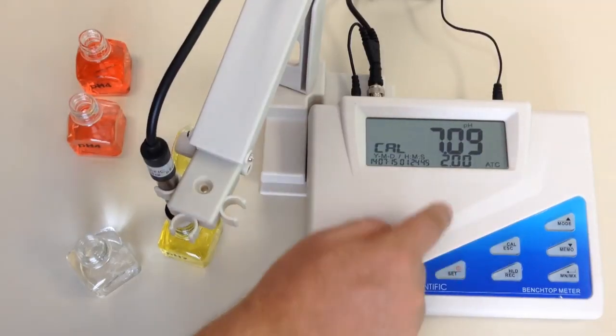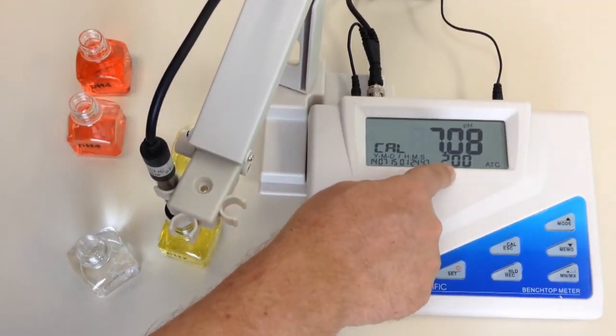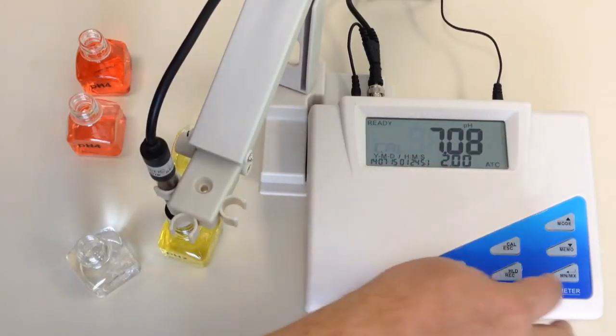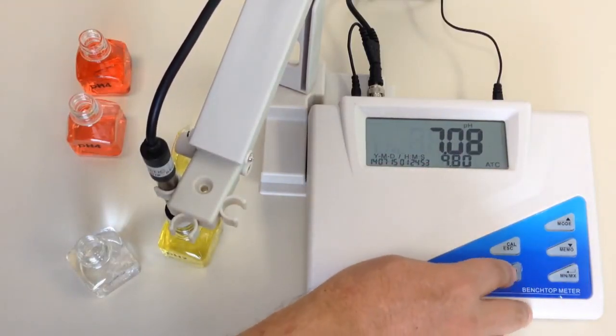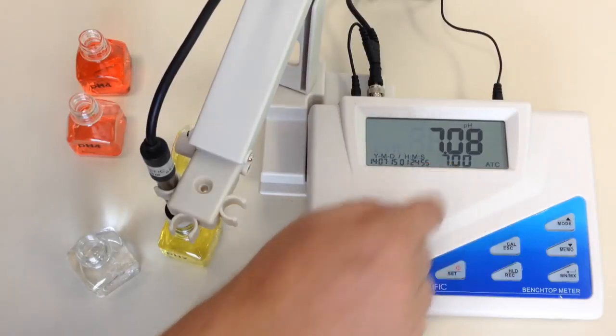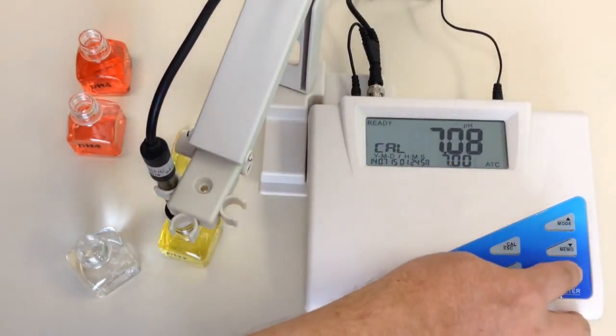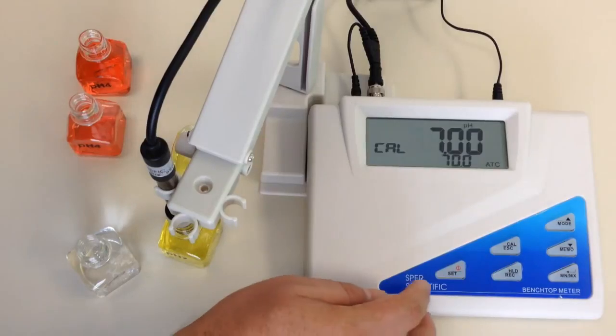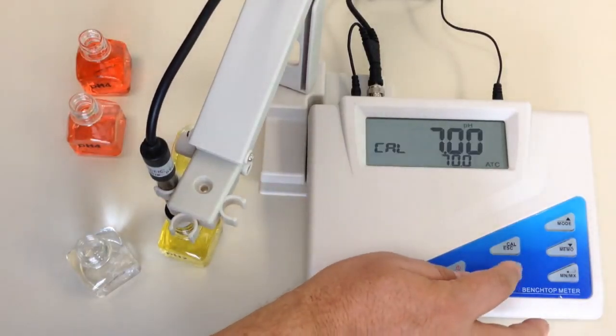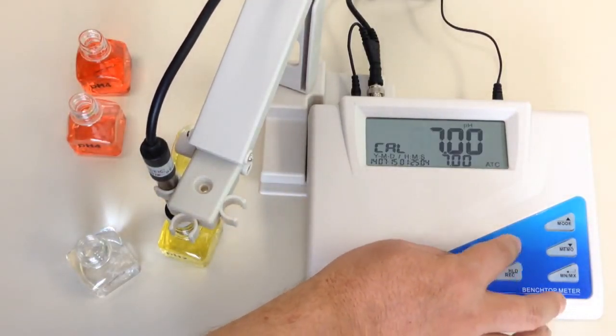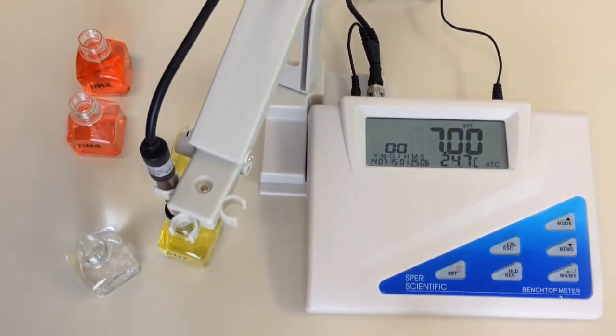I hit calibrate. I'm going to look at the secondary screen, which is, there's two screens here. I'm going to hold this down until it gets to 7.0. As you can see, 7.0 right there. Hit min-max. It's going to start flashing. And it's done flashing. You hit the escape button. It's simply calibrated to 7.0, as easy as that.